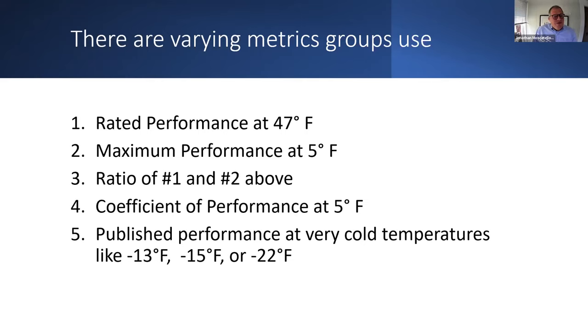Finally, moving along, coefficient of performance. This is an energy efficiency measure. To put it most simply, it's the amount of heat output as a ratio of the amount of energy used to produce that heat. And it's a really great number. Really great cold climate heat pumps produce coefficients of performance of 2 or higher, down even well below 0. The NEEP and Energy Star standard is actually below 2 at 5 degrees. It's not super rigorous, but it's still very efficient, and it's an important number.